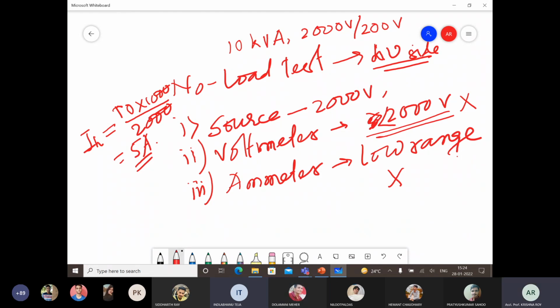Okay, so these are the difficulties we have to face if we want to perform the no load test on the high voltage side. But on the other hand, if we perform this test on low voltage side, then this 200 volt voltage source is easily available. 200 volt voltmeter up to 600 volt, it is easily available. So the voltmeter is not a problem also, and the current rating is 50 ampere, so it's 2 to 6%. That is also a measurable quantity. So ammeter is also not a problem. So that is why we always perform the no load test on low voltage side, not on the high voltage side. Is it clear?